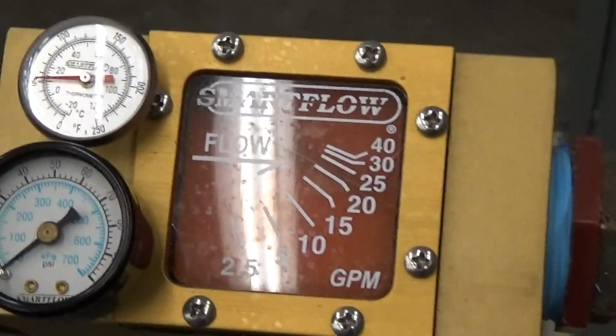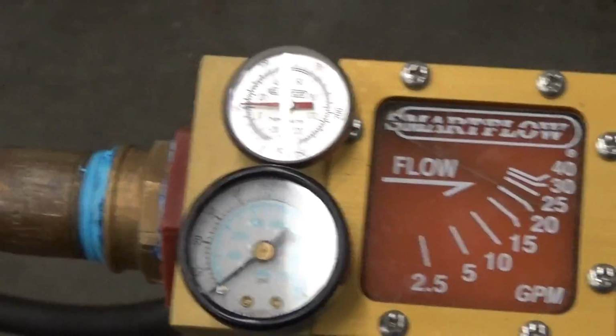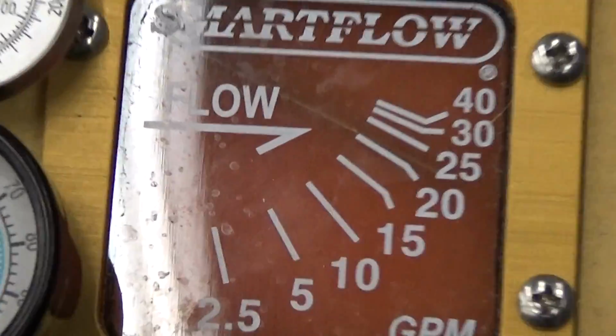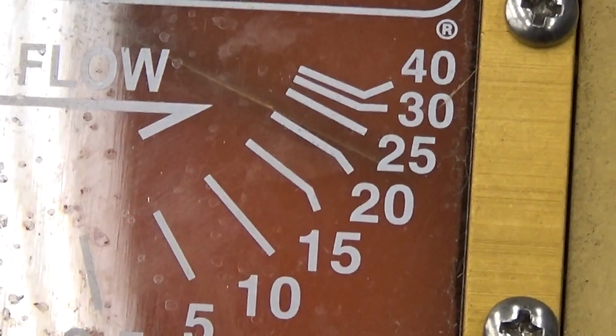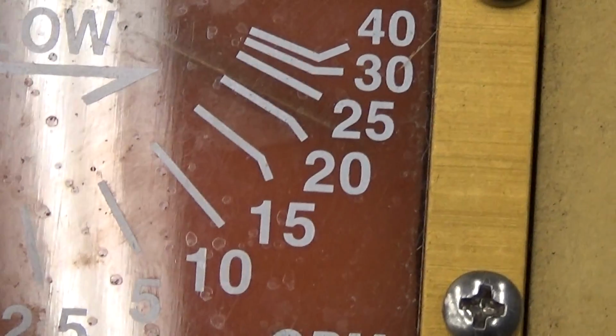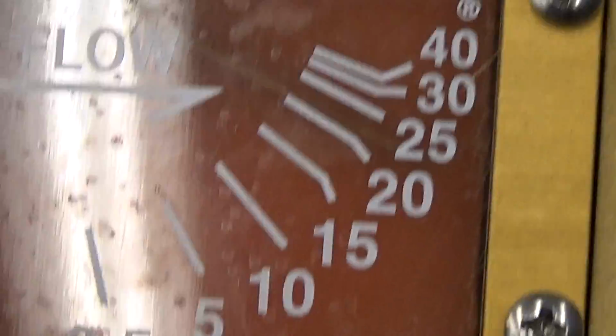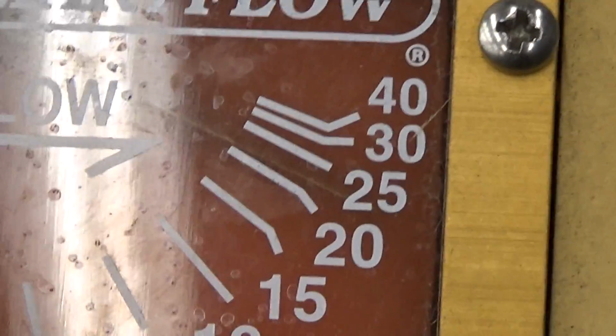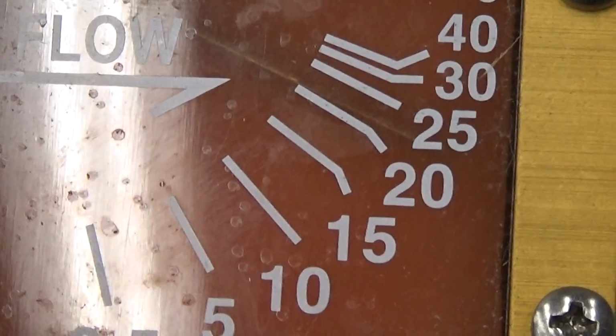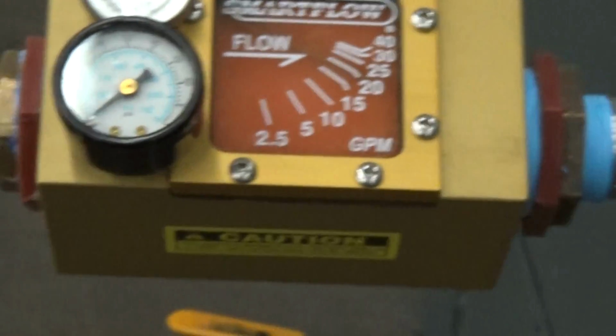If you can do this, anytime you can buy one of these flow meters for $200 or $300 from SmartFlow, it's fantastic. It's always one of the biggest questions with chillers: how much flow do I really have? So right here you see we have just between 20 and 25. As a rule of thumb, rough rule of thumb, you want about 2.5 GPM per ton of cooling. So you probably get it adjusted just about right. You want about 20 GPM for an 8 ton, roughly.